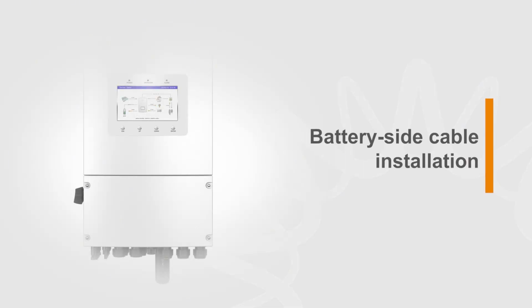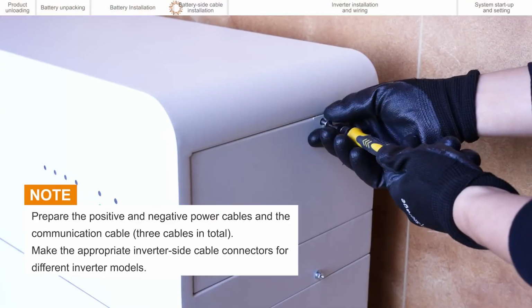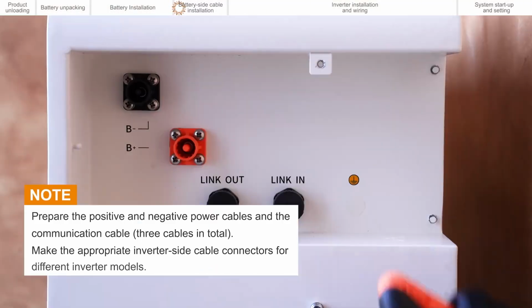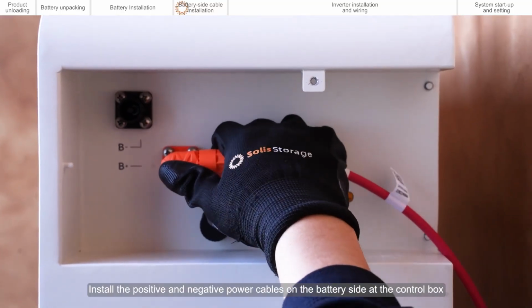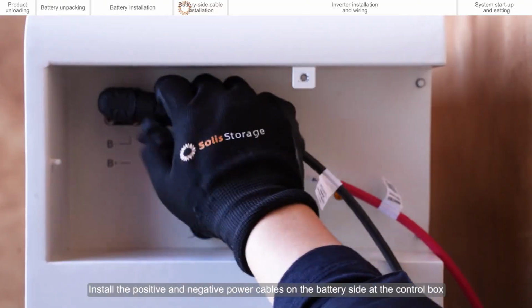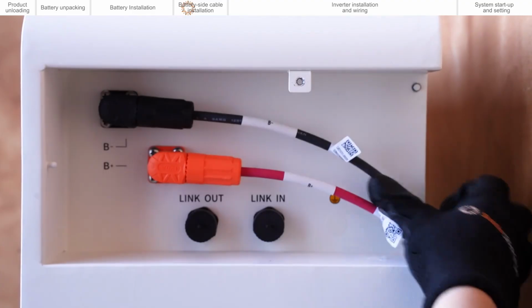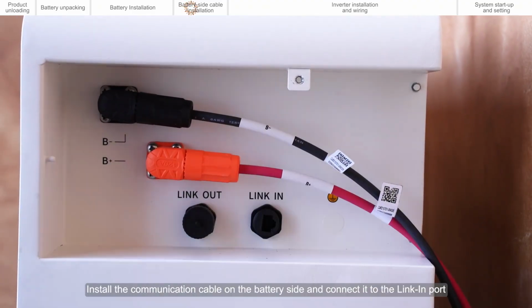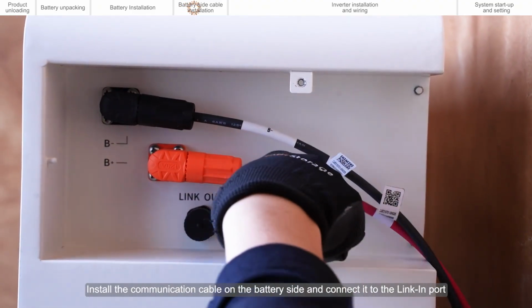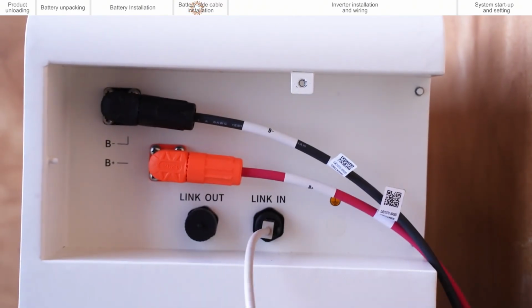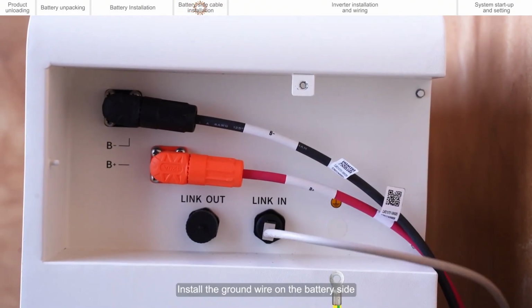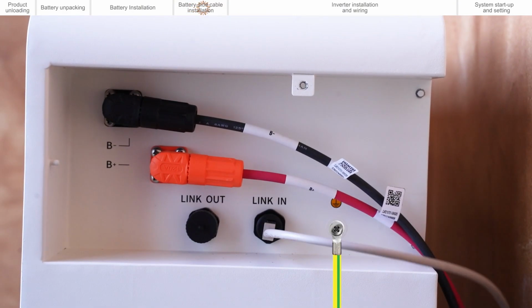Battery side cable installation. Install the positive and negative power cables on the battery side at the control box. Install the communication cable on the battery side and connect it to the link-in port. Install the ground wire on the battery side.